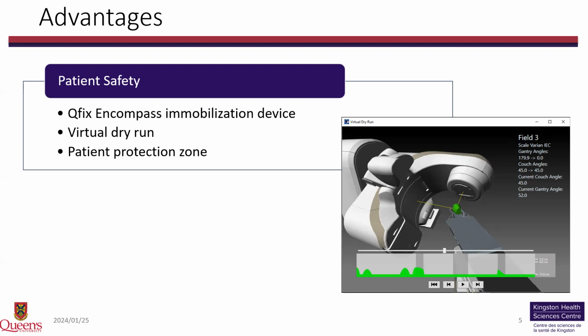Now, in terms of the treatment delivery unit, the patient protection zone is defined as the allowed limit for the couch position. Now, there is also another option available during the planning of the treatment, which is called the virtual dry run. A screenshot of the virtual dry run environment is shown on the right. So this virtual dry run is a 3D animation of the delivery of the treatment that you can visualize and make sure that the automated delivery is going to be collision-free.